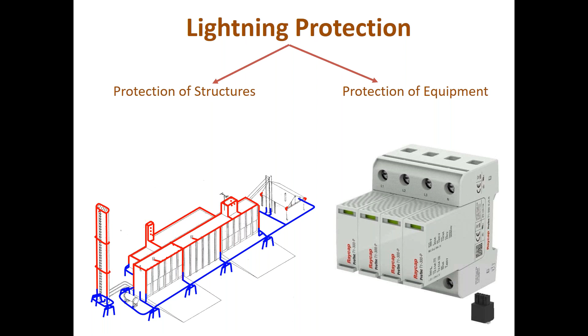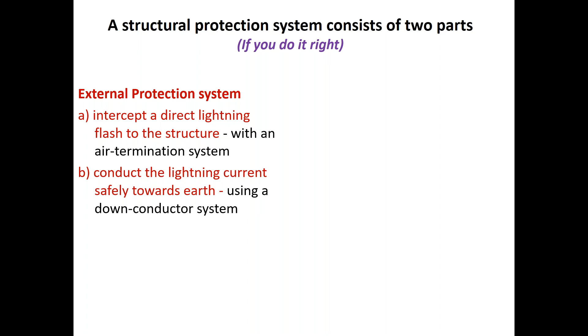If you do it right, a structural protection system consists of two parts: the external protection, which consists of the air termination that intercepts the lightning strike, then the down conductors that conduct the current from top to bottom of the structure and disperse it into earth, which is done by the earthing system.